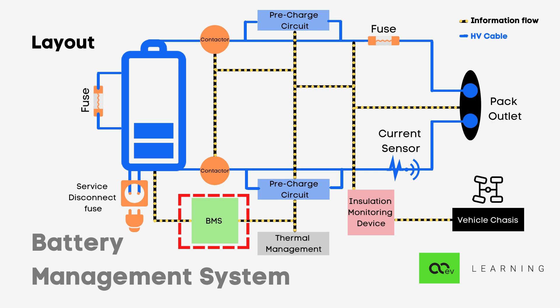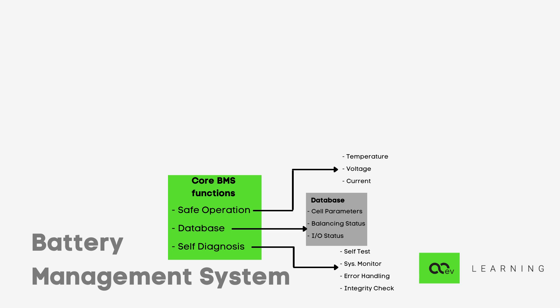Now considering the design of BMS, what is the core function of BMS? First is safe operation, which contains temperature, voltage and current. Second is the database, which keeps a record of cell parameters, balancing status, input-output devices, etc. Third is self-diagnosis, which includes a self-test that checks the BMS each time it reboots, along with system monitoring, error handling if any, and integrity check.